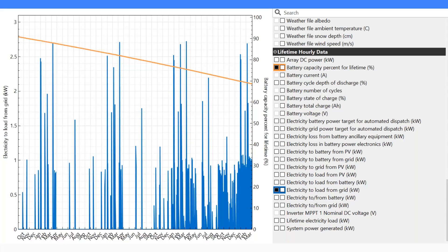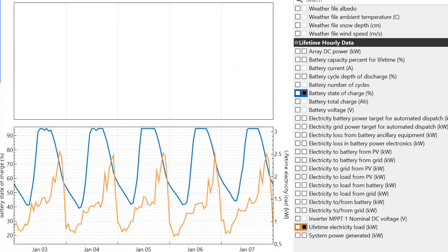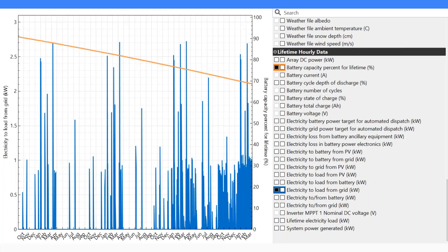This is more or less what the system looks like. The things we track are battery state of charge, lifetime electricity loads — we check that we're not exceeding system capacity too much — and battery life. When battery capacity drops below about 70%, we know we'll have to look at replacing those batteries at some point. You can see the battery curve here.